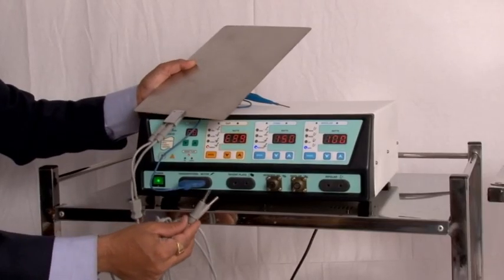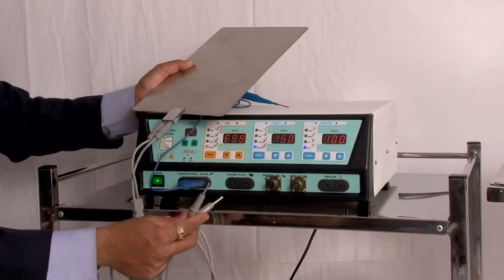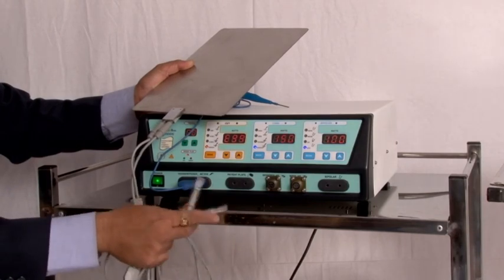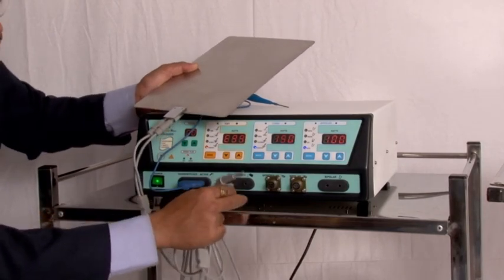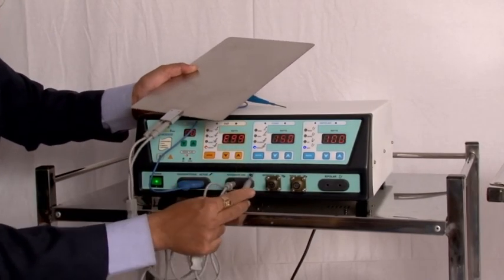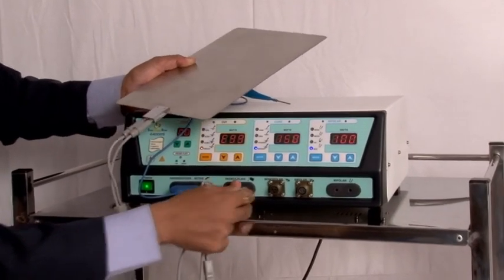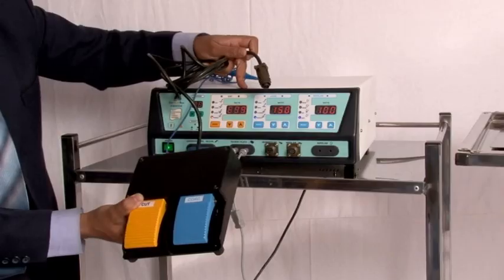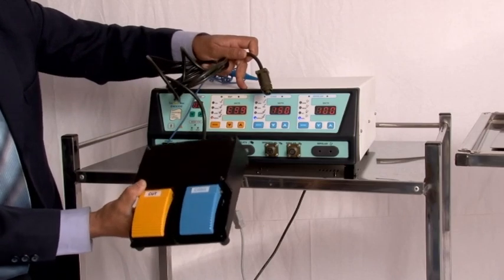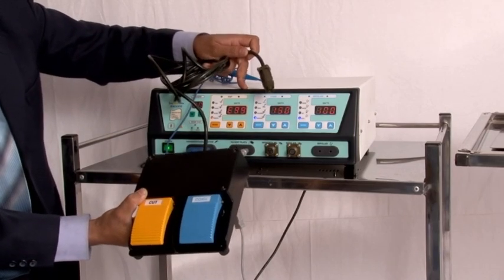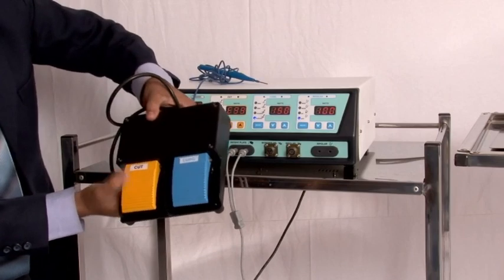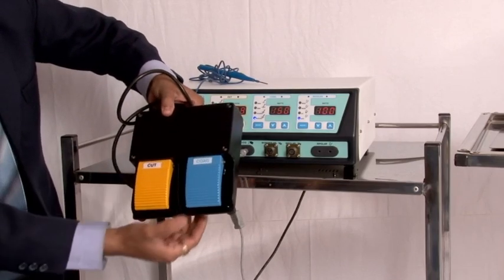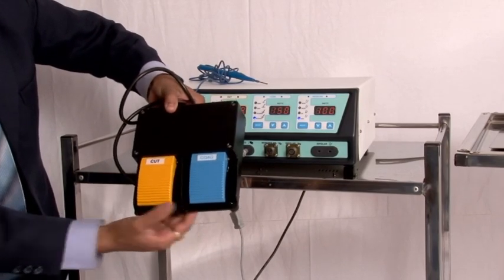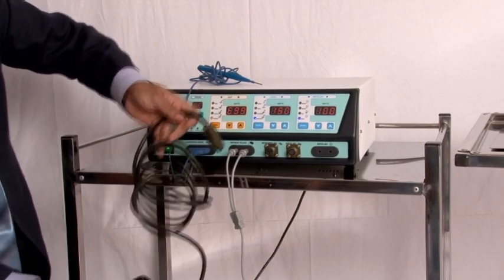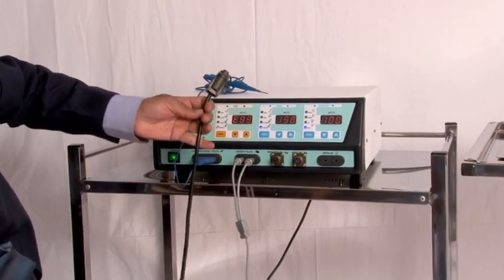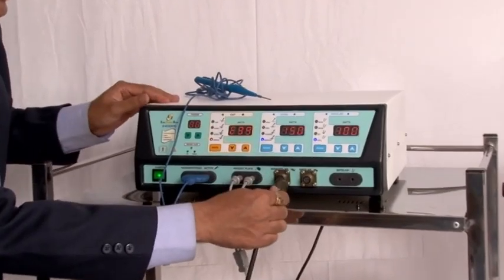The third accessory is reusable patient plate or return plate. It is a stainless steel plate with smooth edges and is attached to the machine at the output jack patient plate. Fourth accessory is monopolar foot switch. It has two paddles. Yellow paddle is for cutting and blue paddle is for coagulation. Monopolar foot switch is attached to the machine at jack monopolar foot switch.